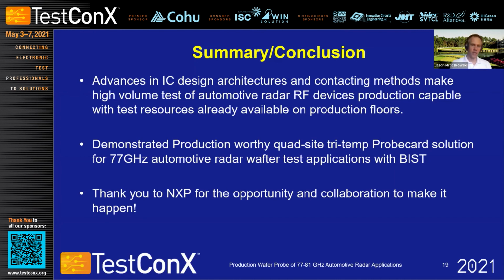Or as was described, we'll provide the calibration substrates that allow you to do actual on-site calibration and even in situ calibration. And then the third methodology that NXP has used for some time is golden units, where they have known good devices that they know the performance of. Simply place those into the device pocket, read the RF parameters, the characteristics of gain and noise floor for those specific devices, and then set any offsets that might be required for a production lot.